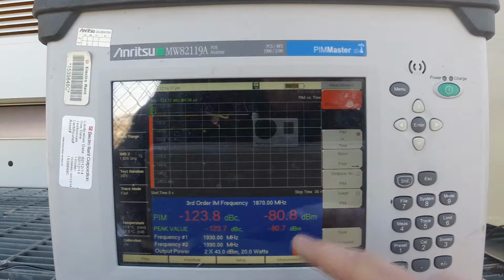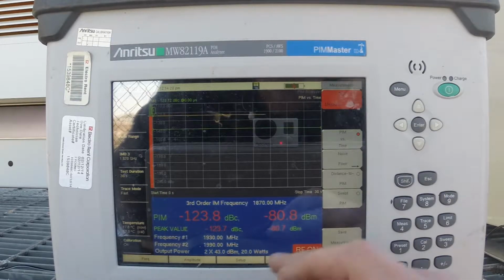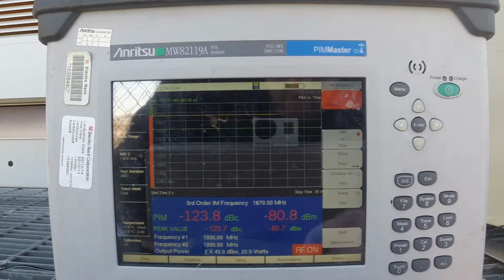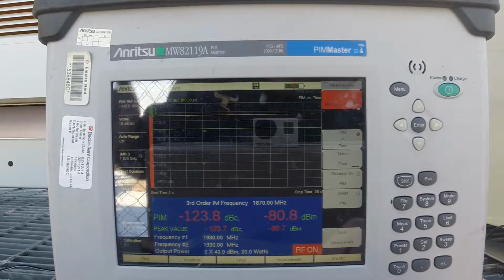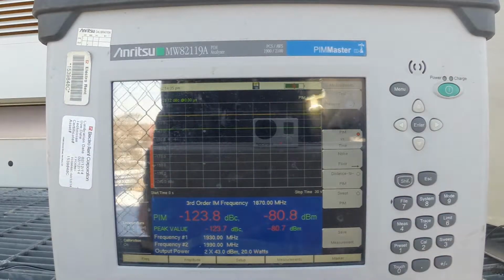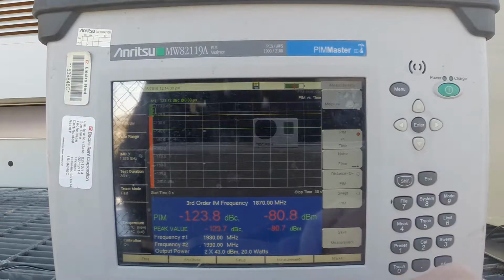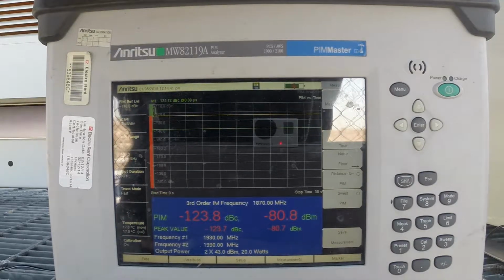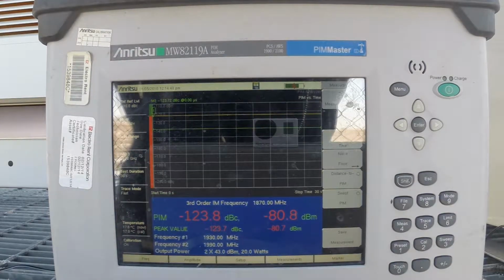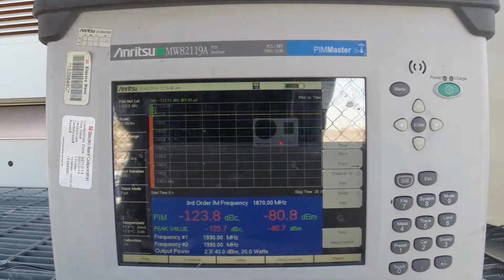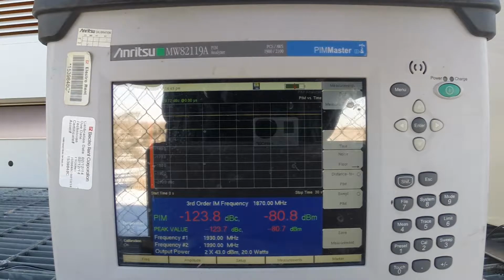And even though it's failing, and don't get me wrong, we're neg 123 dBc, neg 80 dBm, that'd be failing to AT&T and Verizon standards and most standards, but it just shows that our unit is measuring properly. We know our PIM standard is measured at neg 80 dBm, and our unit is reading neg 80 dBm. So after 30 seconds, it automatically turns off, and we can hook up our PIM jumper to make sure that our jumper is good. The jumpers are the most finicky things. We have a lot of Superflex jumpers floating around. There's 2 Anritsu PIM jumpers that always seem to work out very, very well for us.